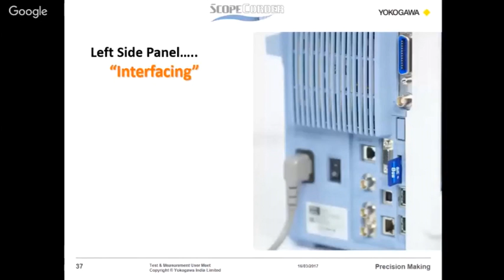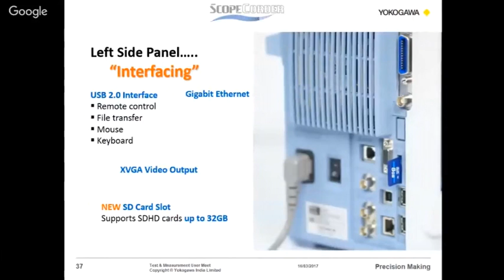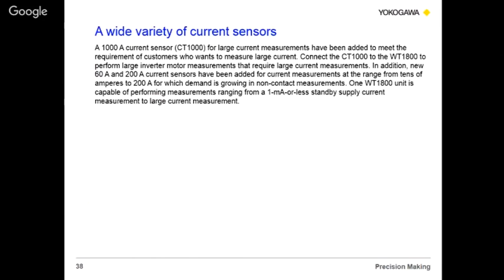Similarly, it has a USB interface for file transfer, remote control, mouse, keyboard, a gigabit Ethernet interface, VGA output, and an SD card slot. Then the variety of current sensors. Normally, when we say we have a high accuracy power analyzer, we should similarly have high accuracy current sensors, because if the current sensor is low accuracy, even with a high accuracy power analyzer it will not be of any use. When the sensing part is low accuracy and the measurement part is high accuracy, our purpose will not be served. So we should have a high accuracy sensor as well as a high accuracy power analyzer. Then only can we measure more precisely.